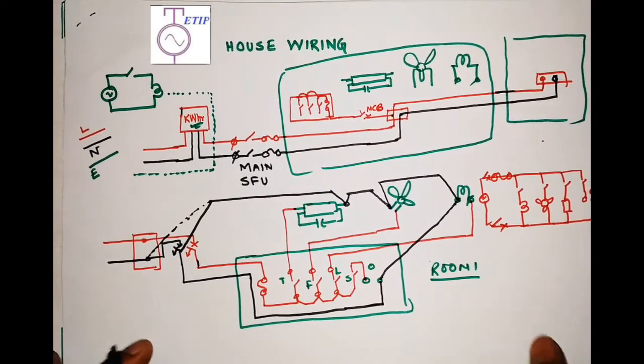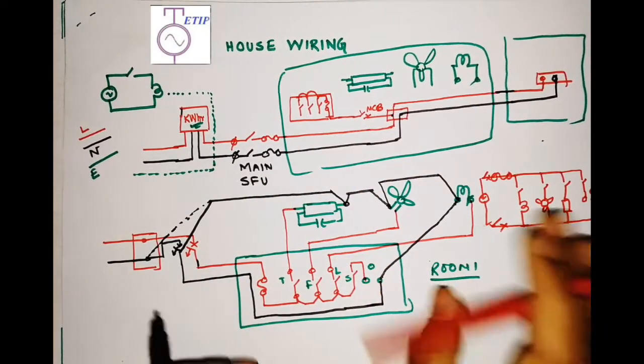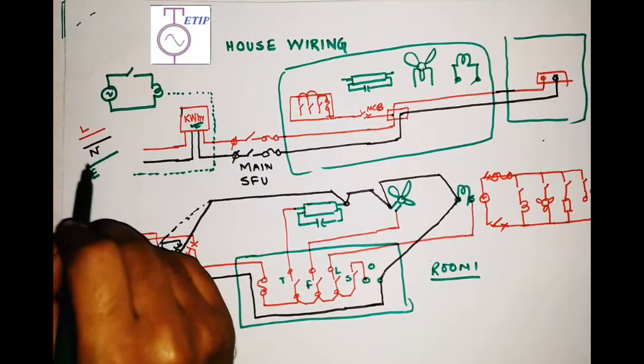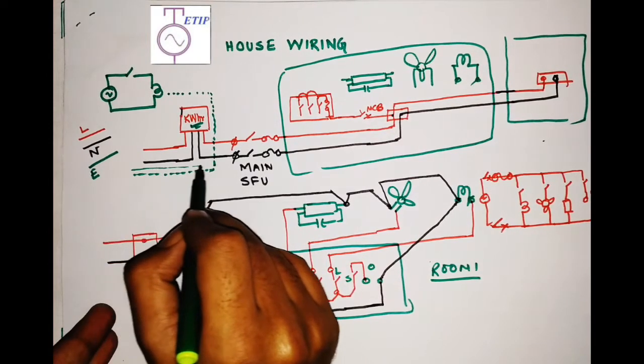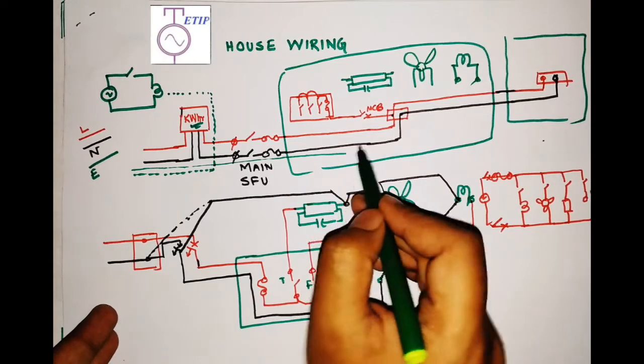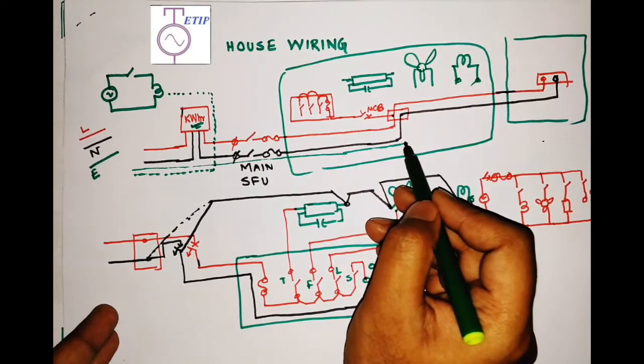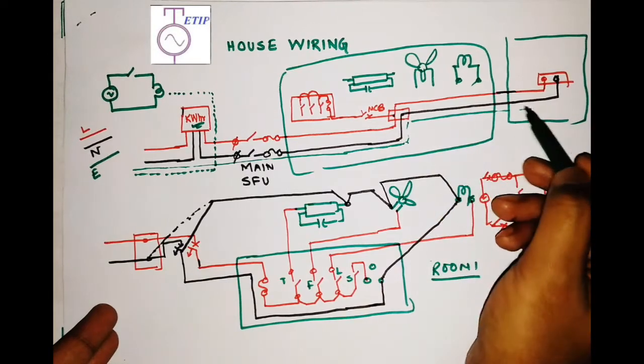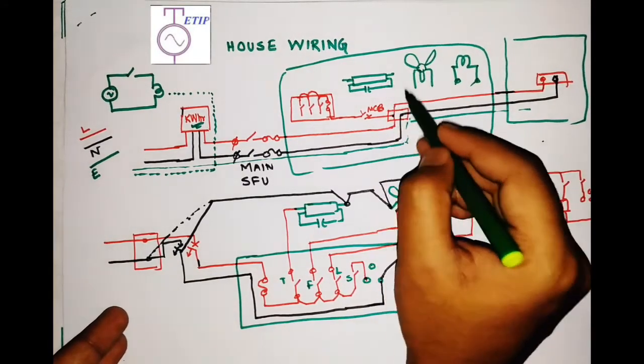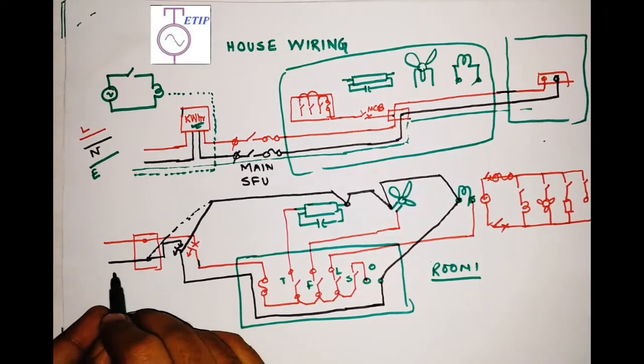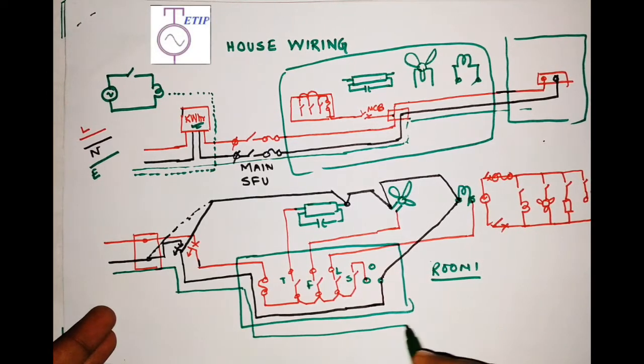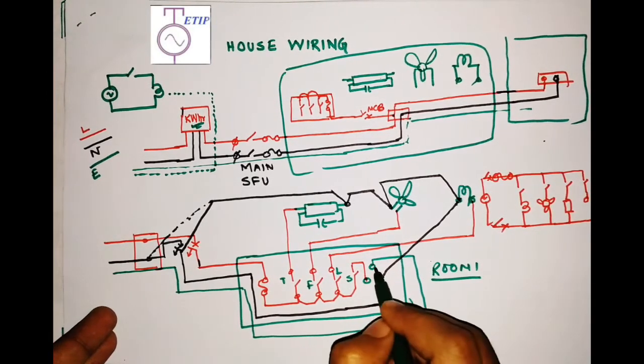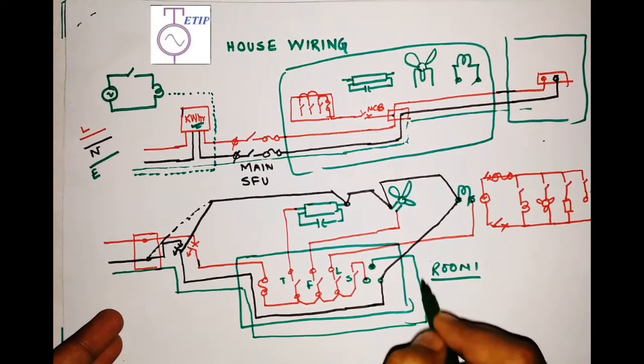This is the basic wiring diagram for house wiring. The earth terminal is also taken along with this wiring and run to each and every room. Ideally it should be connected to all metallic enclosures, but in most domestic applications, the earth wire is connected only to the socket earth terminal — the third terminal of the socket.